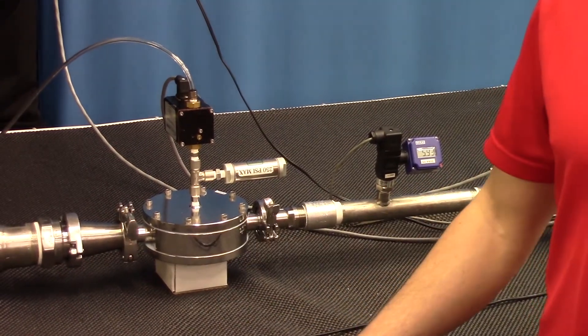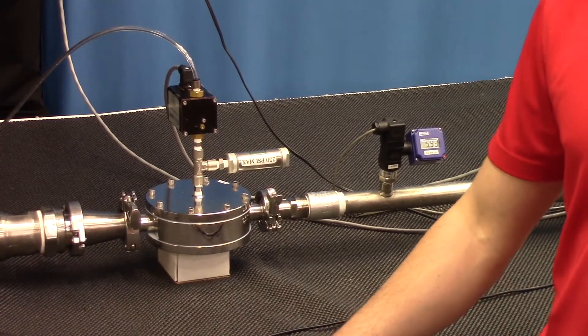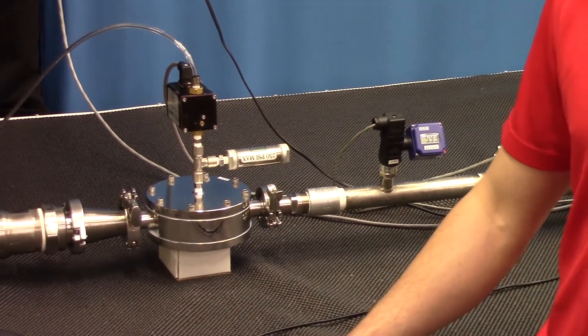We'll plot the pressure performance in LabView and report the valve's turndown ratio from low to high flow across three flow meters. Let's go see this in action.